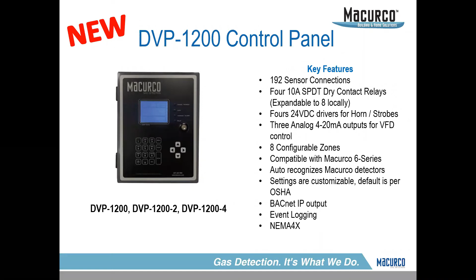The other thing that I want to talk about when we're getting into these are the types of outputs. We have all of this on our data sheet, first of all. So these control panel data sheets are broken down as such. Pretty easy to read. If you're looking for a specific output, you just associate that with the right panel. So going from top to bottom, you've got your analog connections, your digital, total zones, which is becoming a big issue. And then your relays, your outputs, which are your single 24 volt DC outputs, your BACnet outputs. And now we're getting into more of the VFD or the ventilation side of control, which is your 4 to 20 milliamp outputs. Again, that's that linear output that'll give the gas concentration per its output.